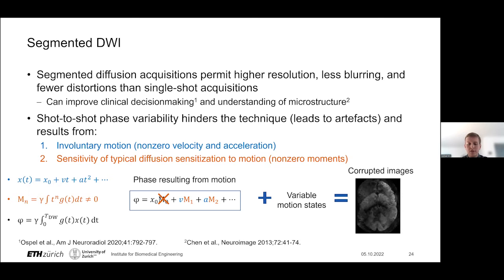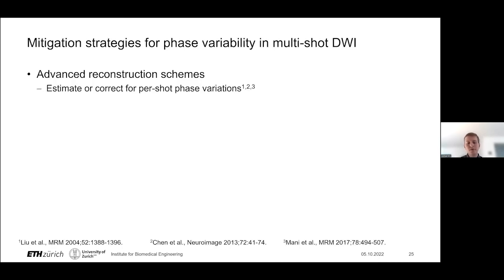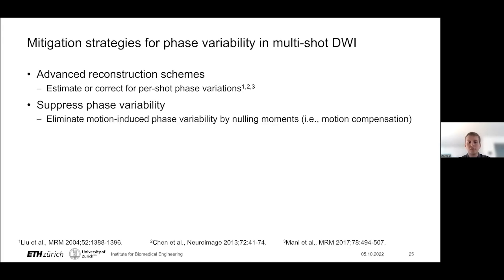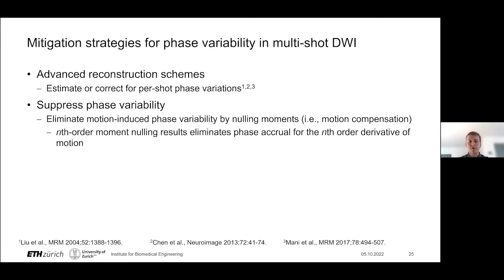Across shots of an interleaved acquisition, we would have variable motion states and therefore different values of phase accrual, ultimately resulting in corrupted images. This shot-to-shot phase variability is typically handled on the reconstruction side, where per-shot phase variations are estimated and corrected for. However, we are also interested in suppressing the phase variability directly at the source — using diffusion gradient waveforms with null moments, which would reduce the phase variability. This process we can call motion compensation, meaning nulling through the N-th order moments of the diffusion gradients would eliminate phase accrual for up to the N-th order derivative of motion.